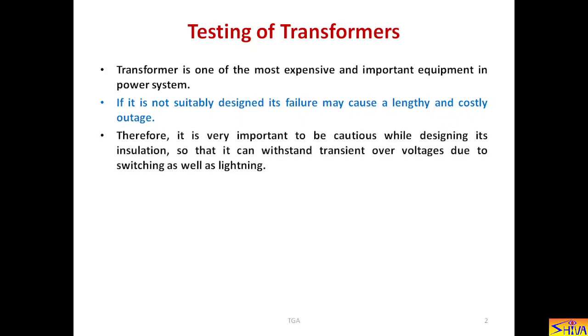Therefore, it is very important to be cautious while designing its insulation so that it can withstand transient overvoltages due to switching as well as lightning.